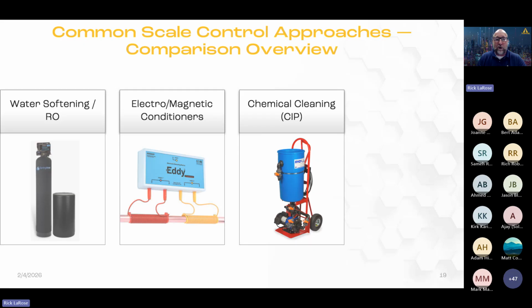Let's try to keep the scale from forming. CIP is a reactive strategy. Now your heaters are scaled, your system is scaled, you've got a problem, you've got to shut it down and hit it with some acid to get that scale out, get the heavy fouling done. It works great, Rydlyme is a wonderful way of removing scale quickly from a scaled up heater, but you have to consider you're handling chemicals and what you're going to dispose of. It's a recurring expense that's maybe not predictable. You don't know when it's going to scale up and you'll have to do it, or it becomes something you do on a regular PM basis.